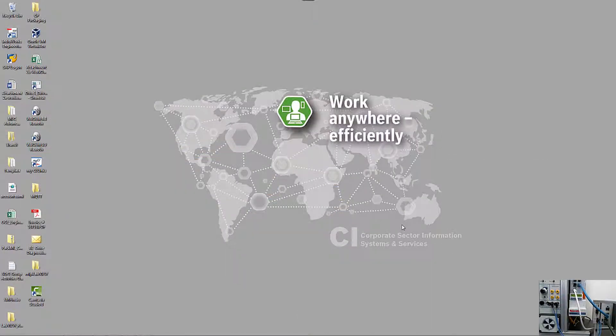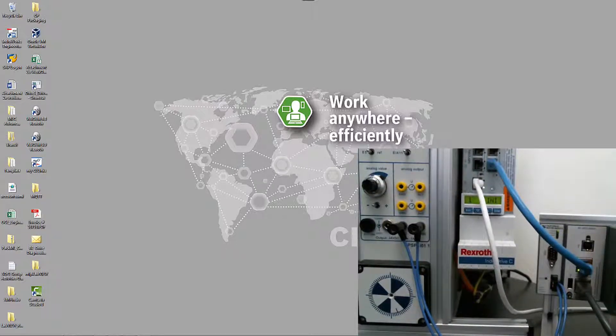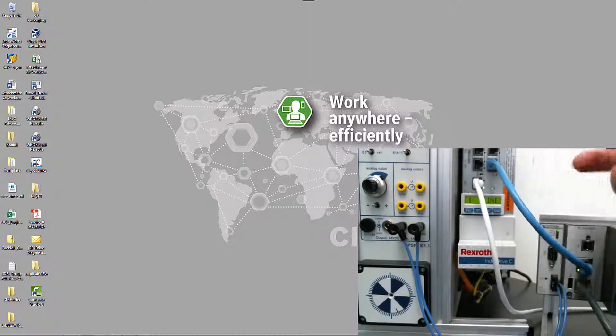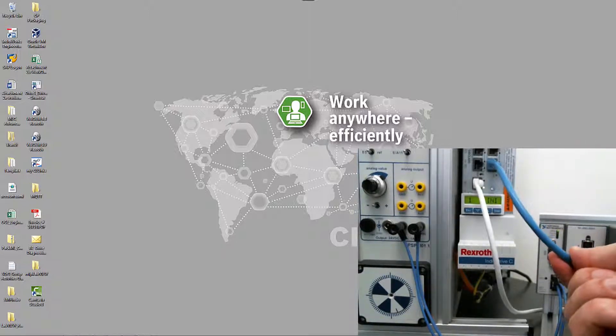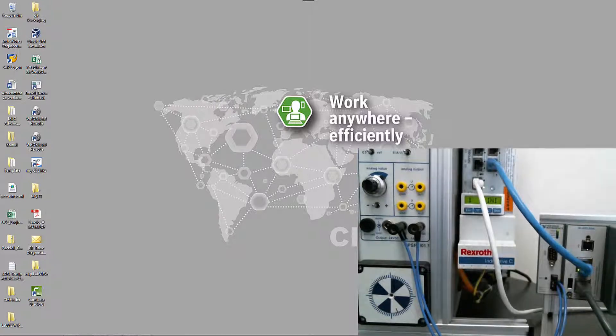Before we can begin to do any programming in LabVIEW, we will need to configure both the CRIO controller as well as the drive itself to accept EtherCAT as the real-time communication.